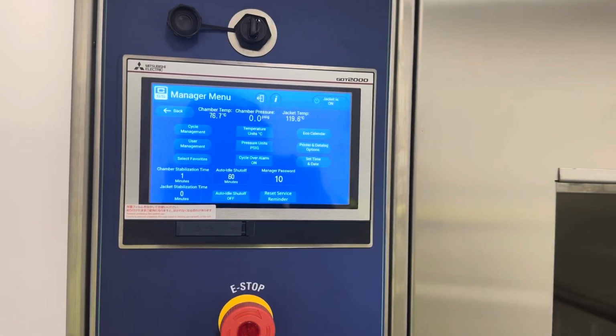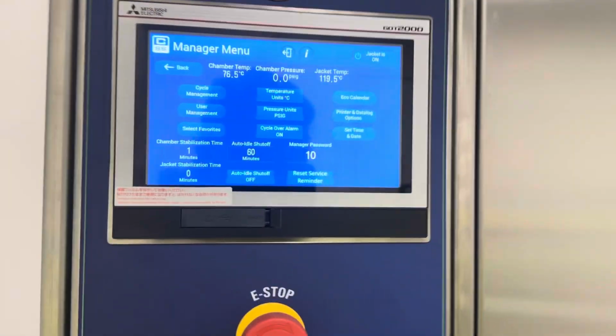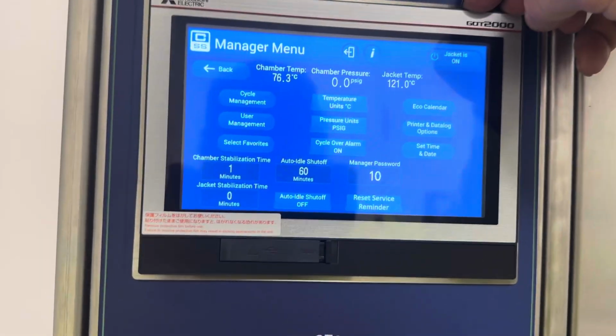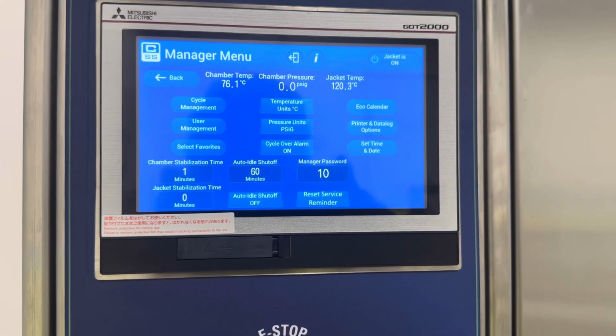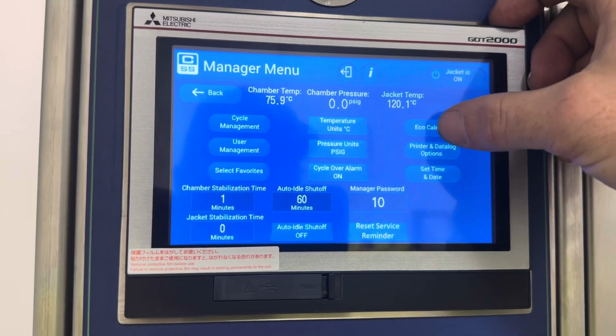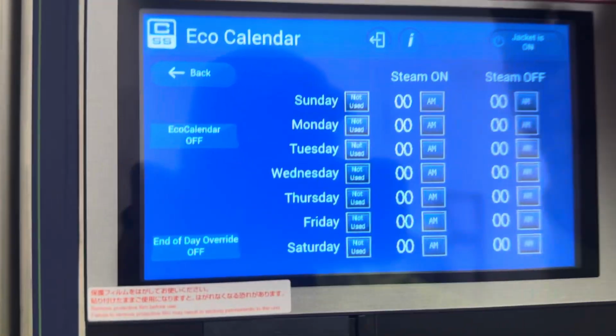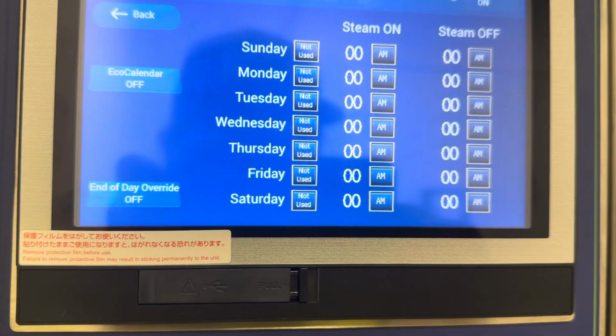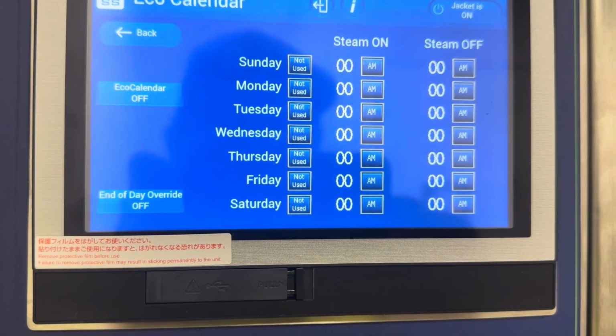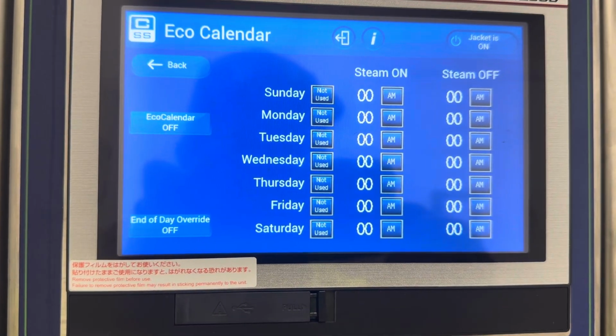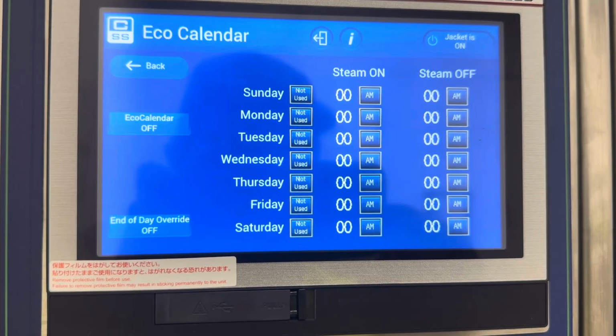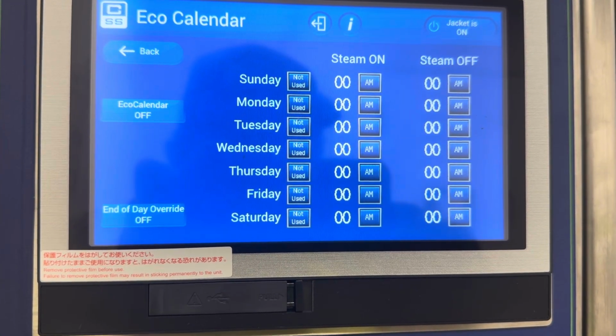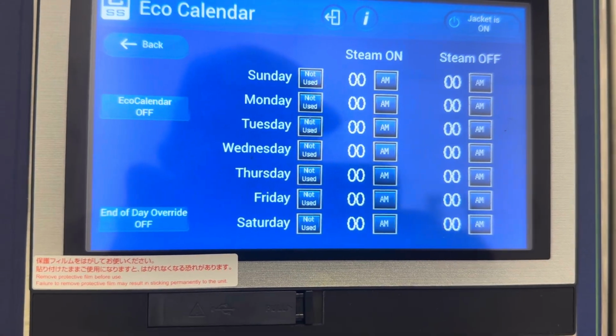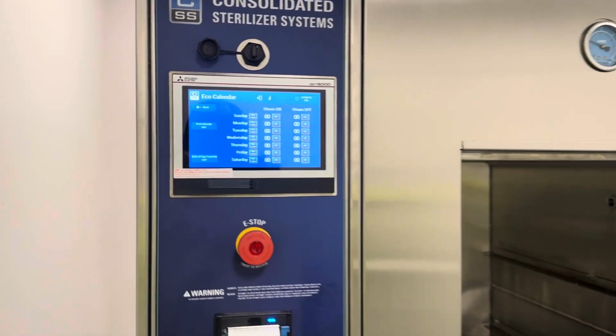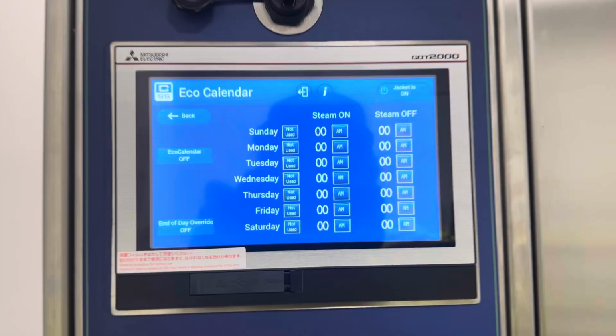Earlier in the training I mentioned that to turn the machine on, you press jacket on. That is correct. However, this machine also has a function called the Eco Calendar, where you can pre-program this machine to come on at certain times and also go off at certain times. It is very important for this machine not to stay on 24/7 — I'll repeat that one more time — it is very important for this machine not to stay on 100% of the time. It needs to turn off. This machine is equipped with an automatic blowdown for the steam generator, and it will never blow itself down if you do not turn the machine off.